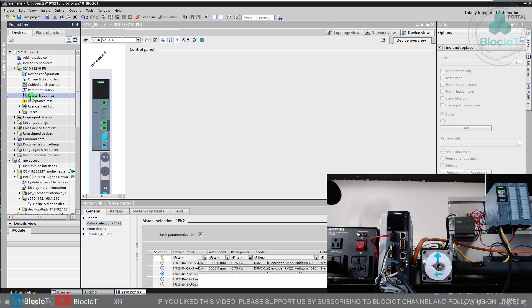Okay, now the drive that is added to our project, the first step is going to be rotate and optimize. And for sure, you need to go online with the drive because we are going to bump the motor or rotate the motor. So as you can see here on the lower right side, you have a live view of the motor, and please pay attention to the shaft and the movement and any error that might occur on the drive or the PLC. So after opening rotate and optimize, click activate.